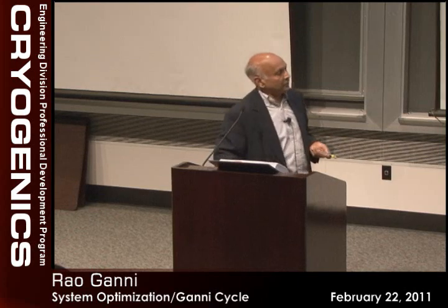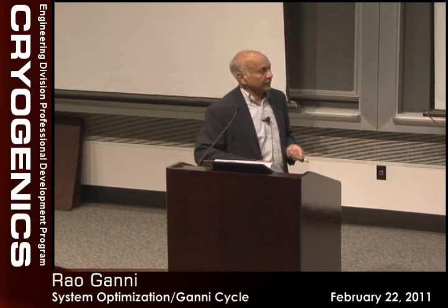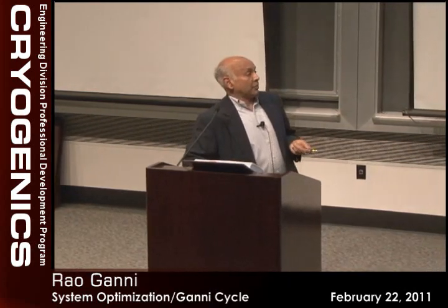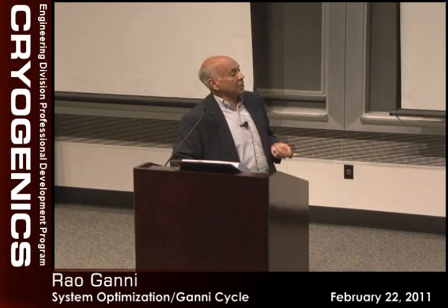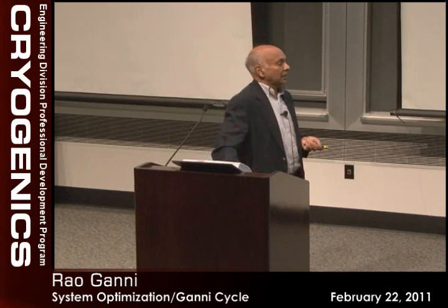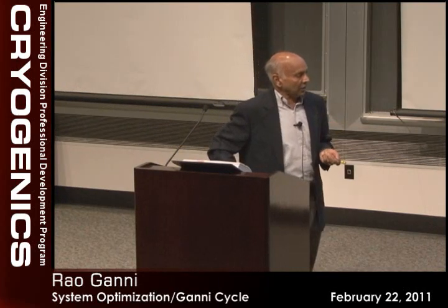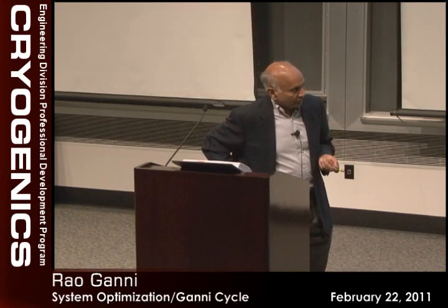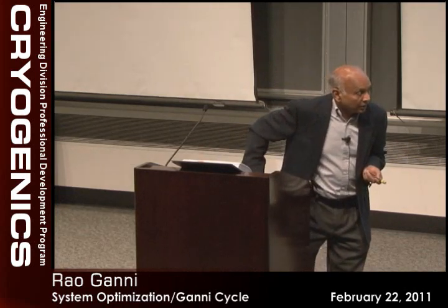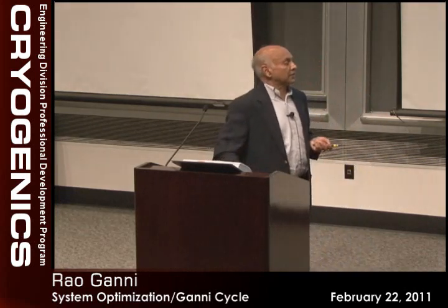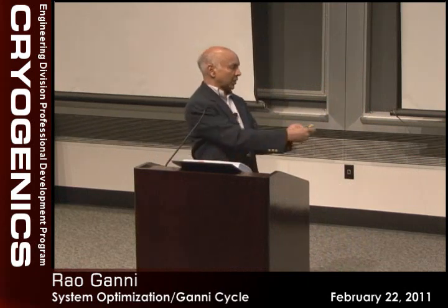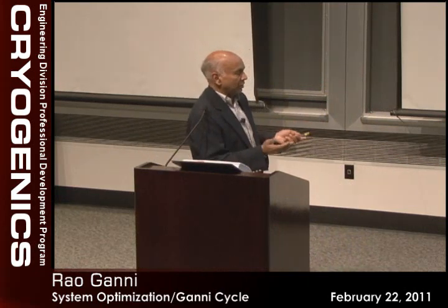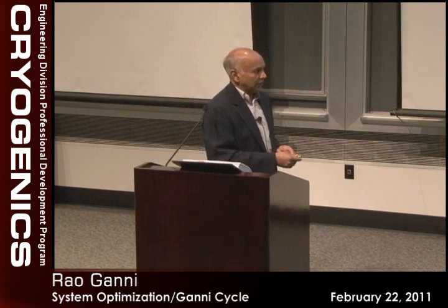About 16 now? Yeah. And what limits how far you can go with the current system? Ours will be 20 for the CHL2. That's the components. CHL2, in our mind, is the ultimate of what we can do in Carnot, at 20%. That's where, because of the limitations, we have the cold compressors already done. Those are given. We can't change them. They're around 68% efficient, less than 70.